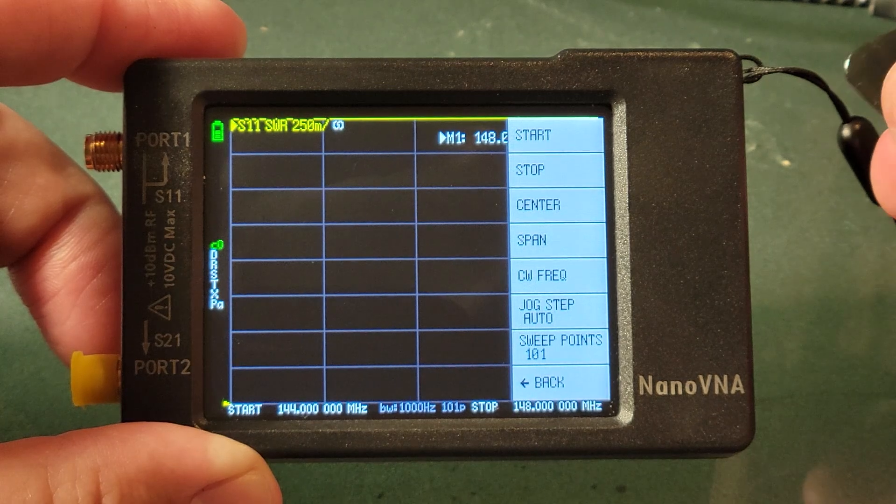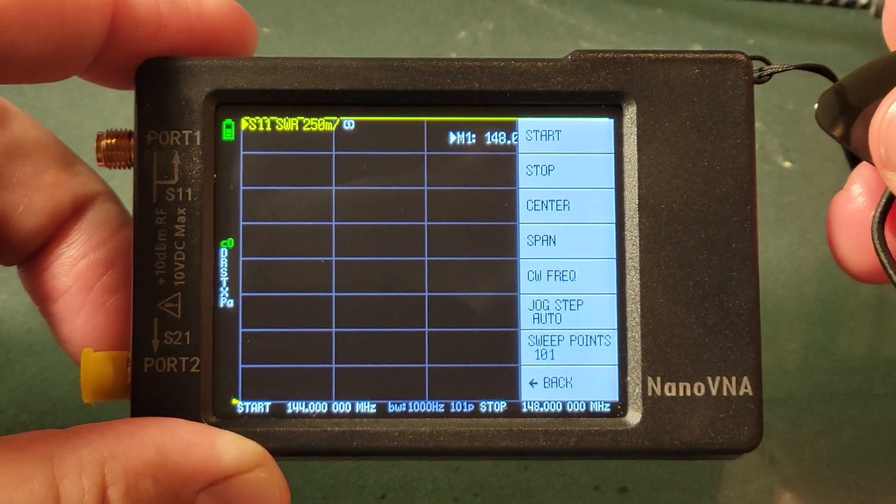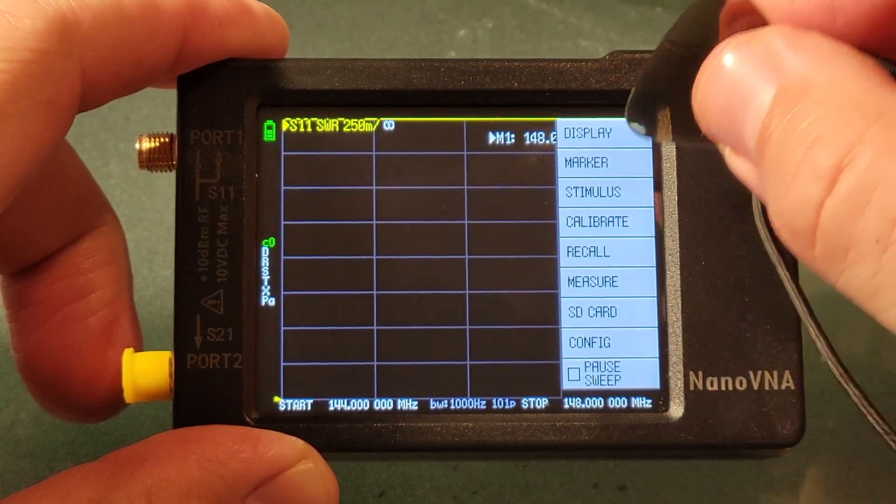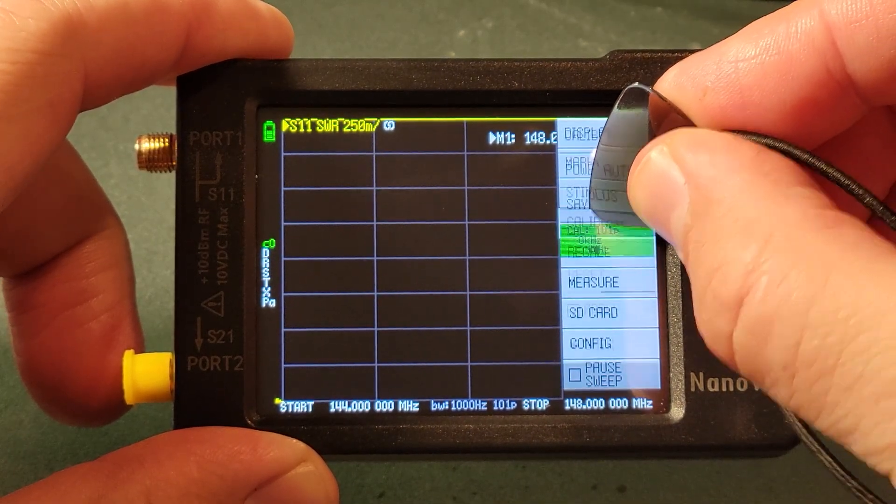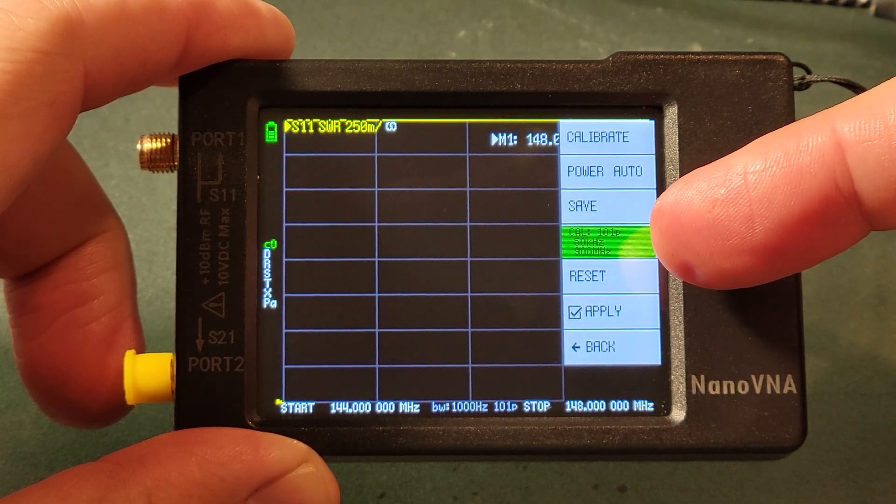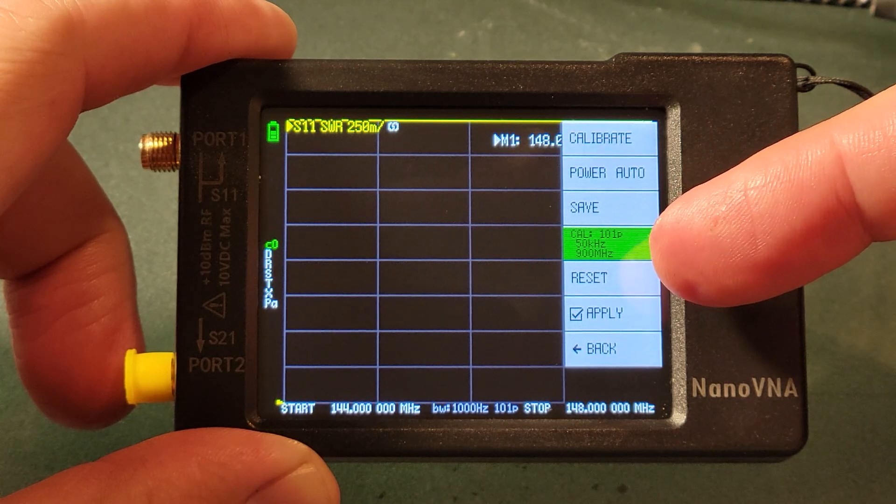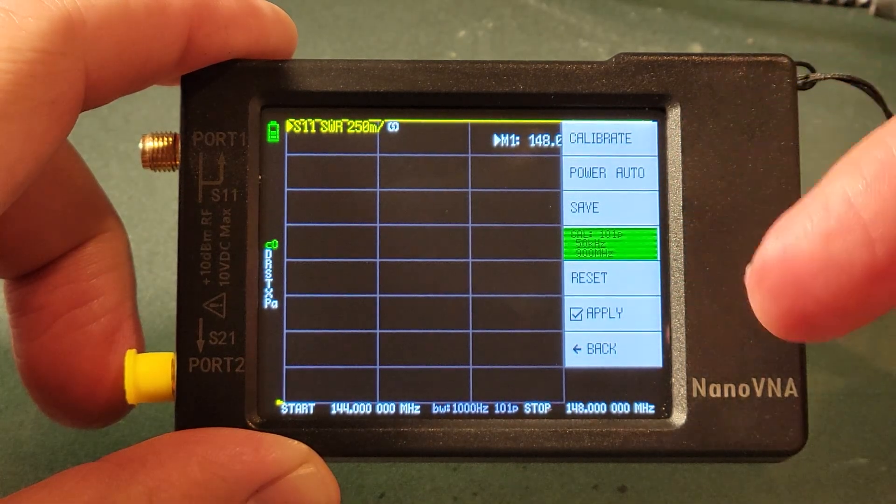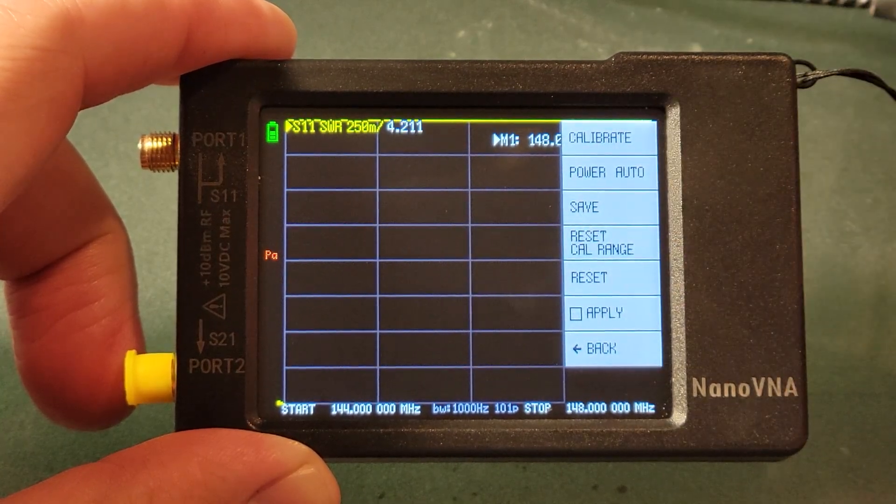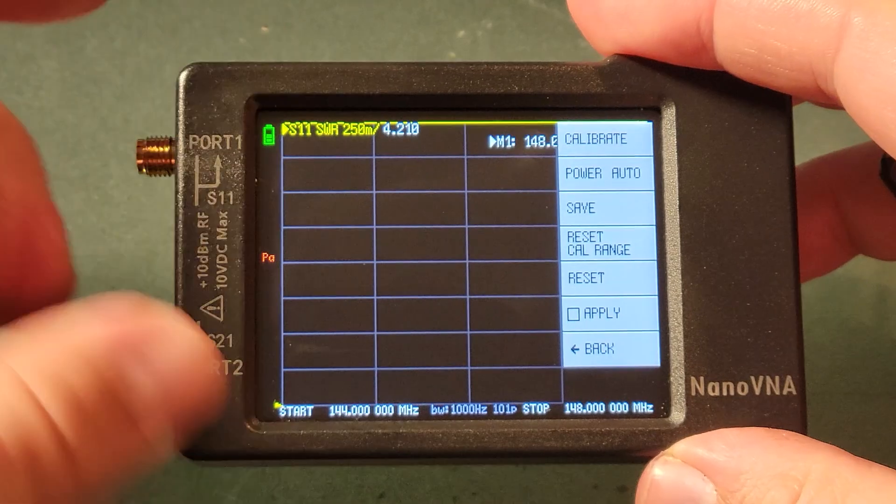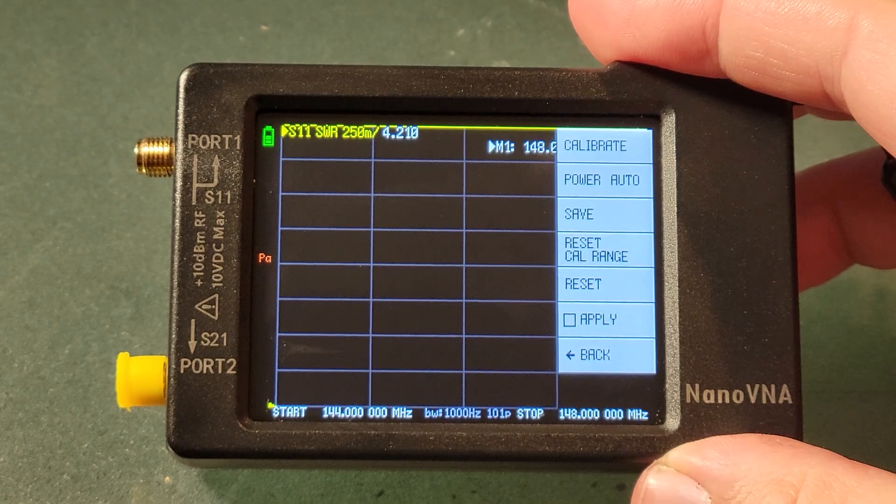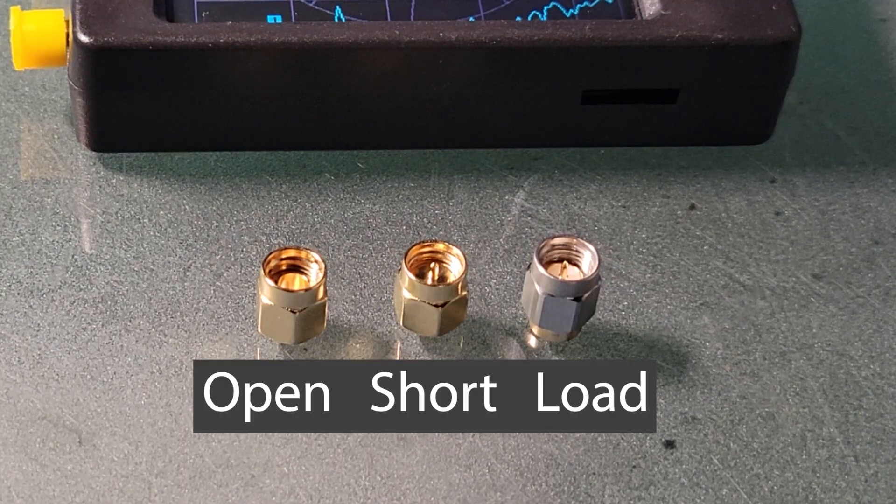The next thing we need to do in order to get an accurate reading we must calibrate the device for the start and stop point that we've set up. Go down to calibrate from the main menu. Notice here there is a calibration reading. It says 50 kHz all the way up to 900 MHz. We already have a calibration that is being used so we want to clear that away before we initiate the next step of our process. You can also see on the other side here some letters indicating the same thing. And we'll be using the caps that come with your kit.